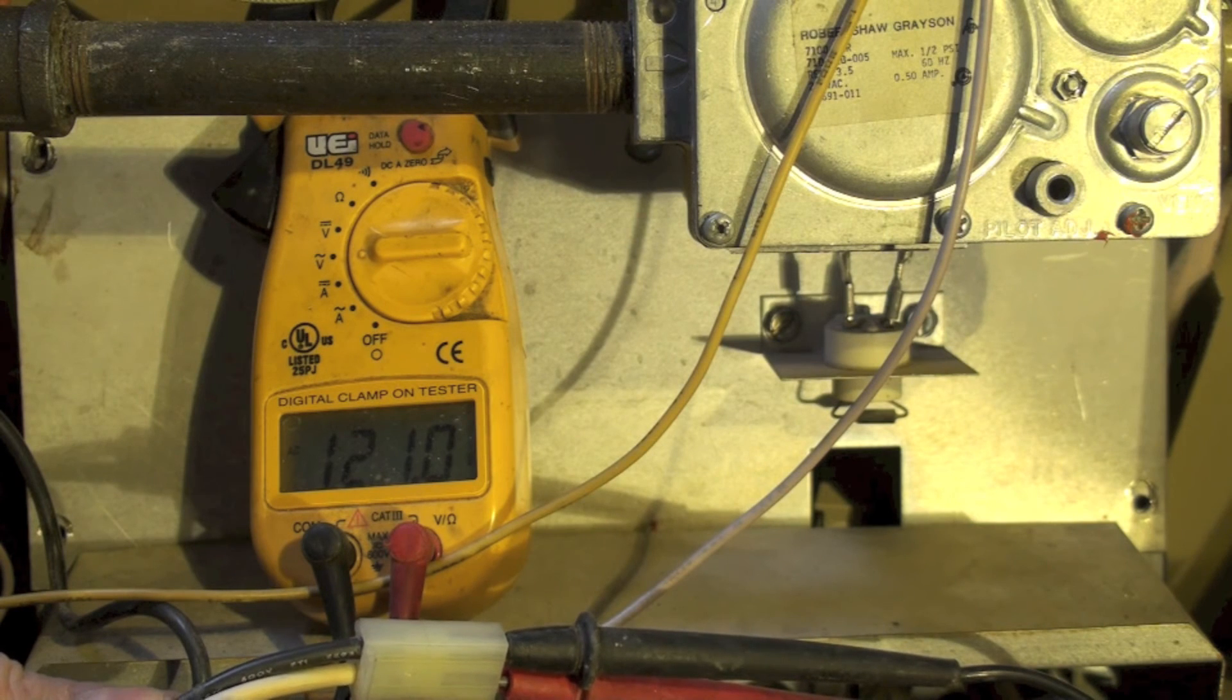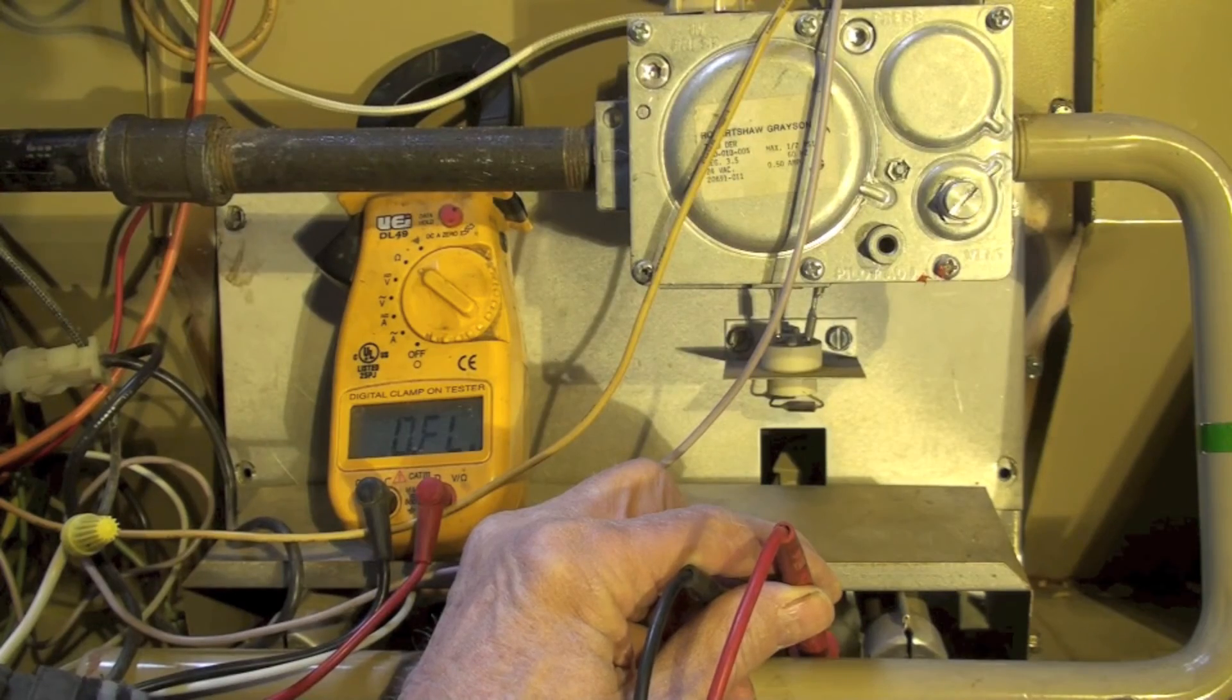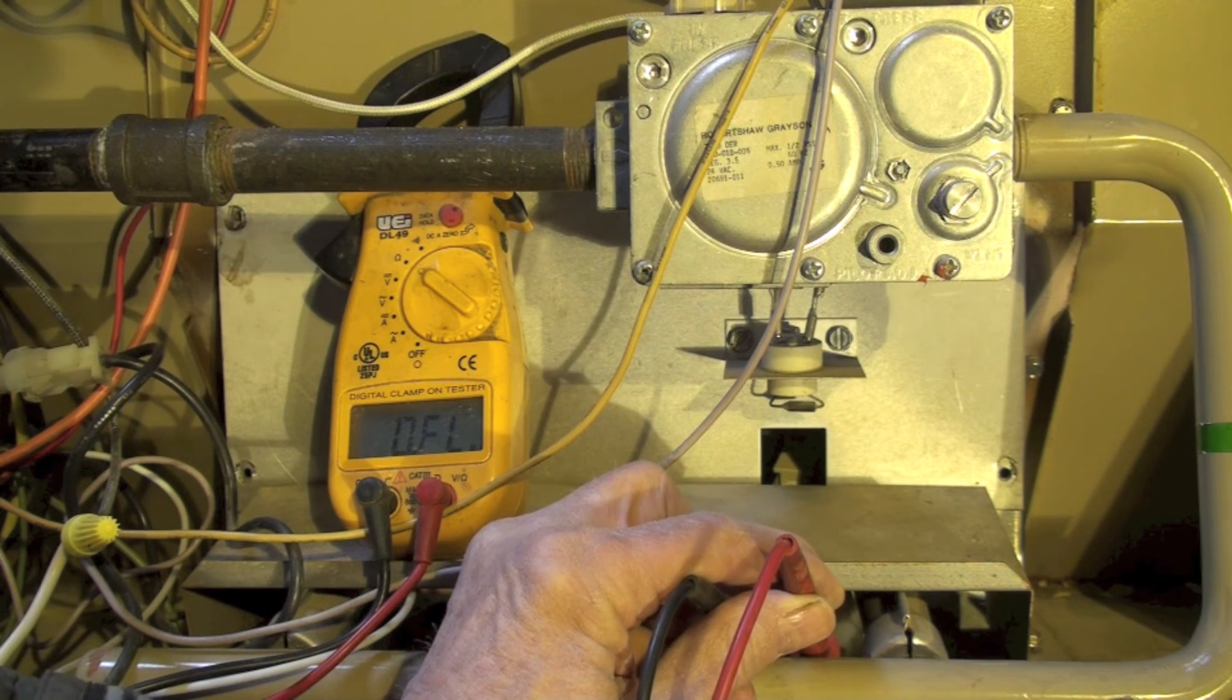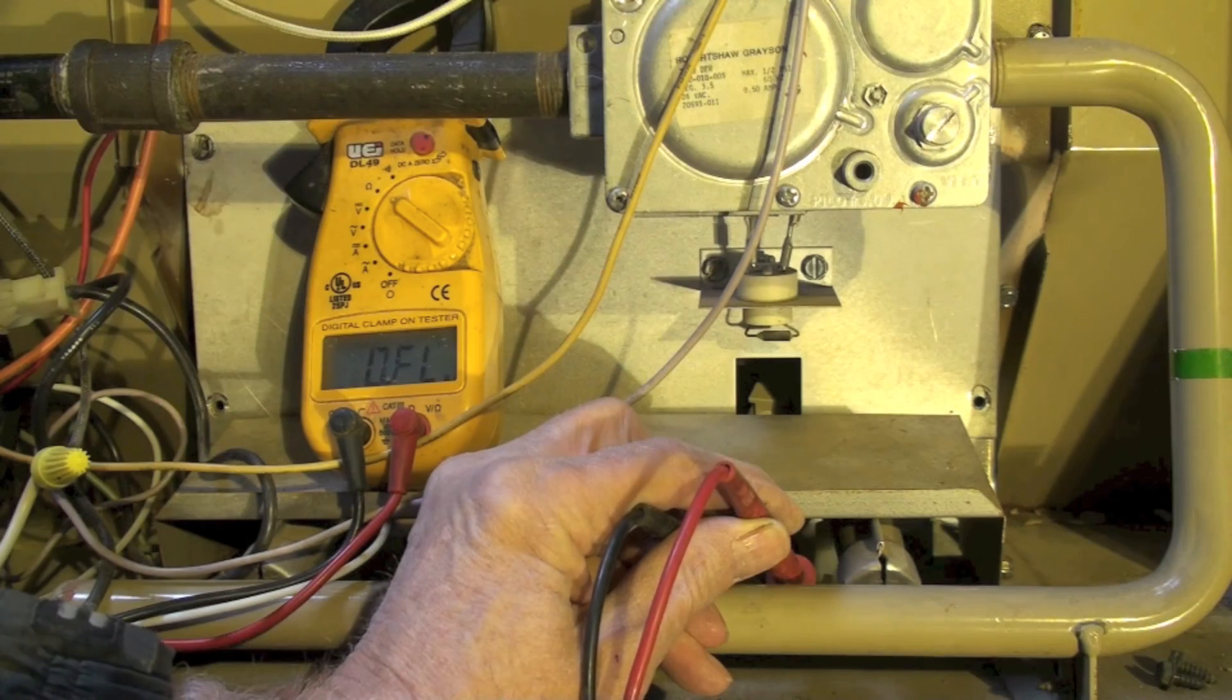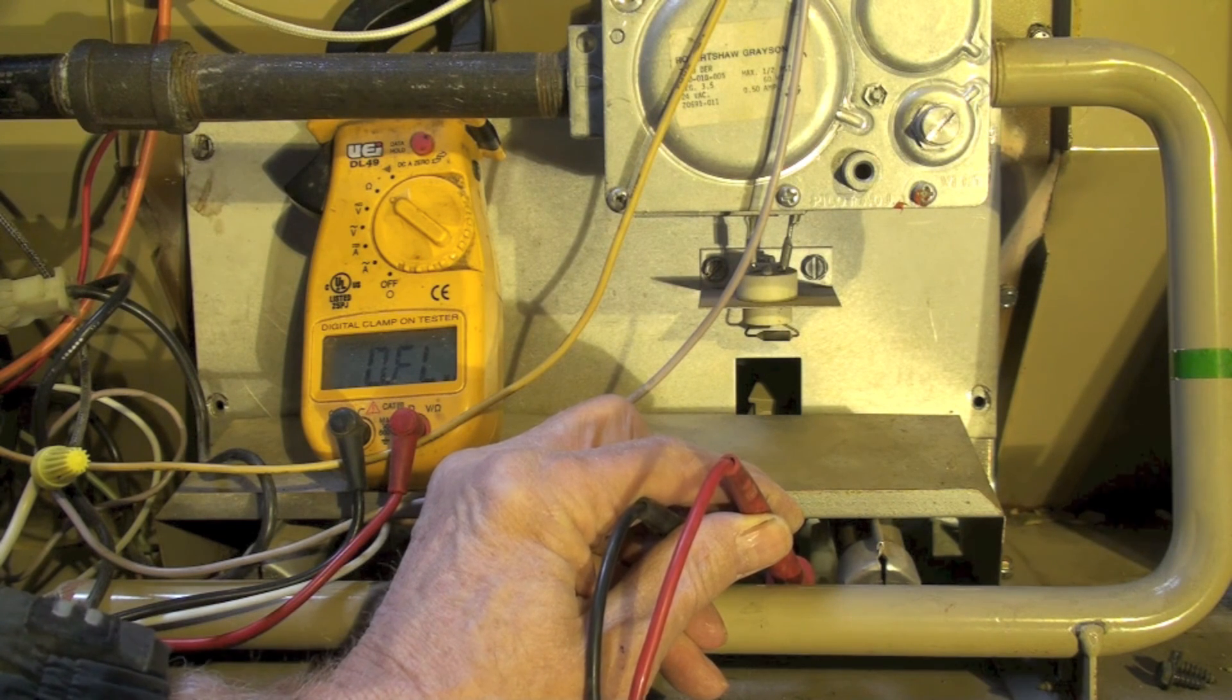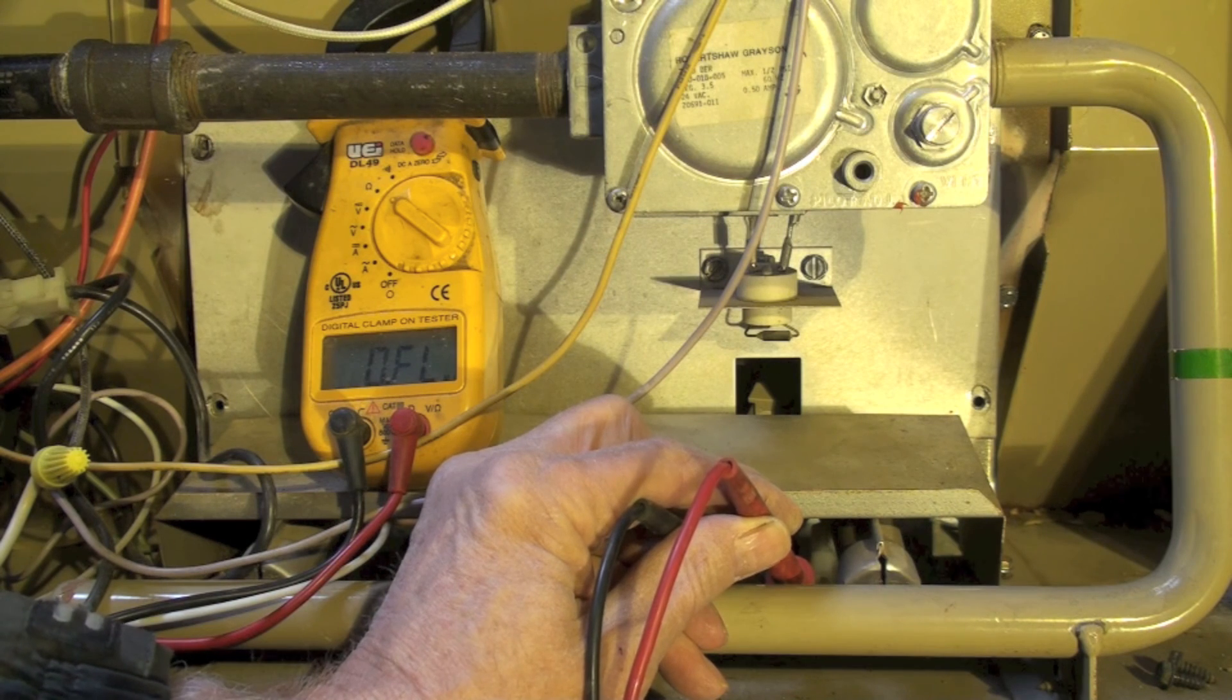So let's check out the hot surface igniter. Here I've put my probes on the hot surface igniter wire - it's a little hard to see there. I'm showing open on the meter, so I've diagnosed this thing: the hot surface igniter has failed. We need a new hot surface igniter.